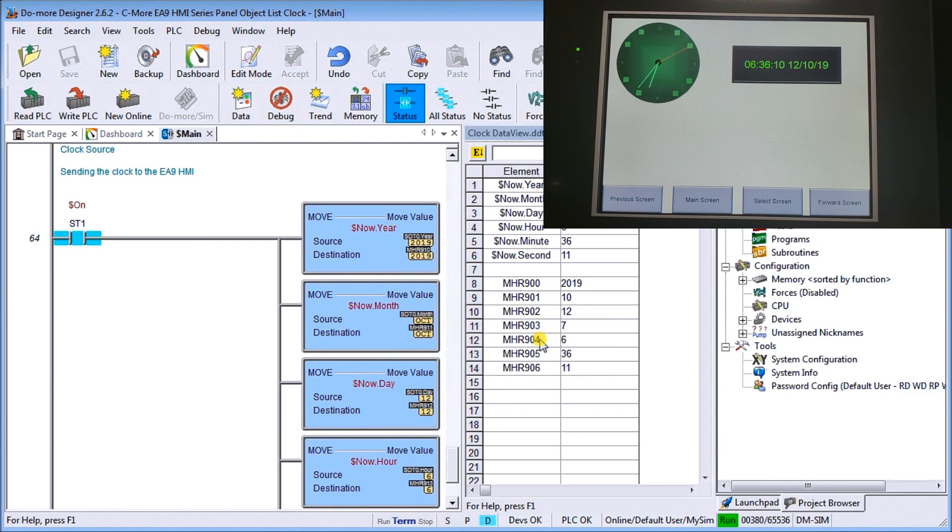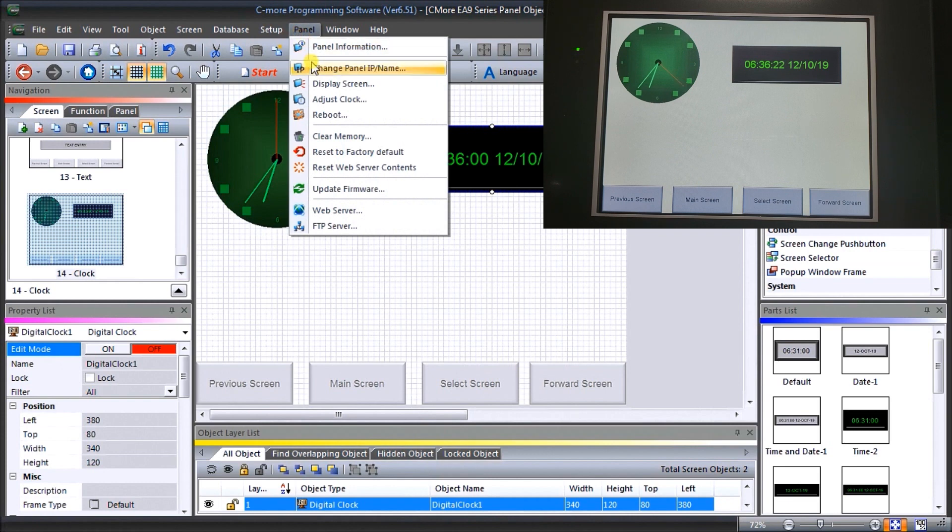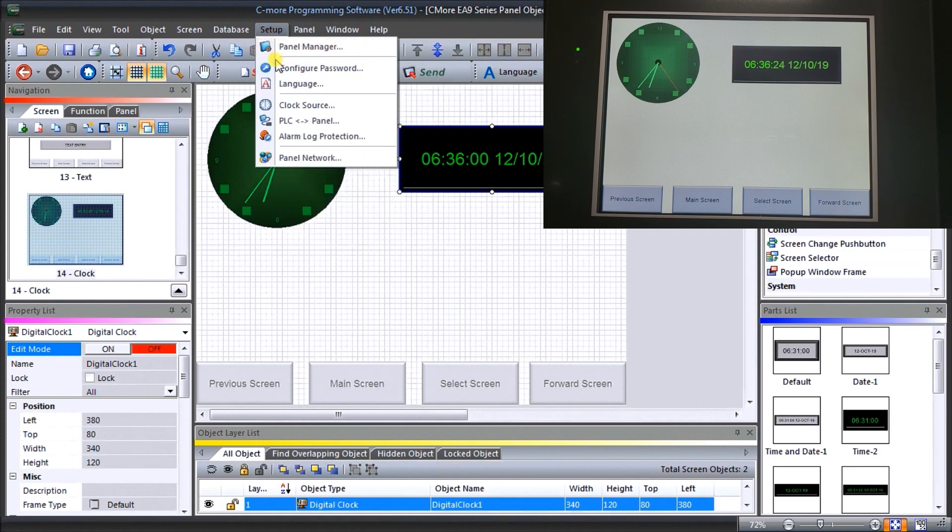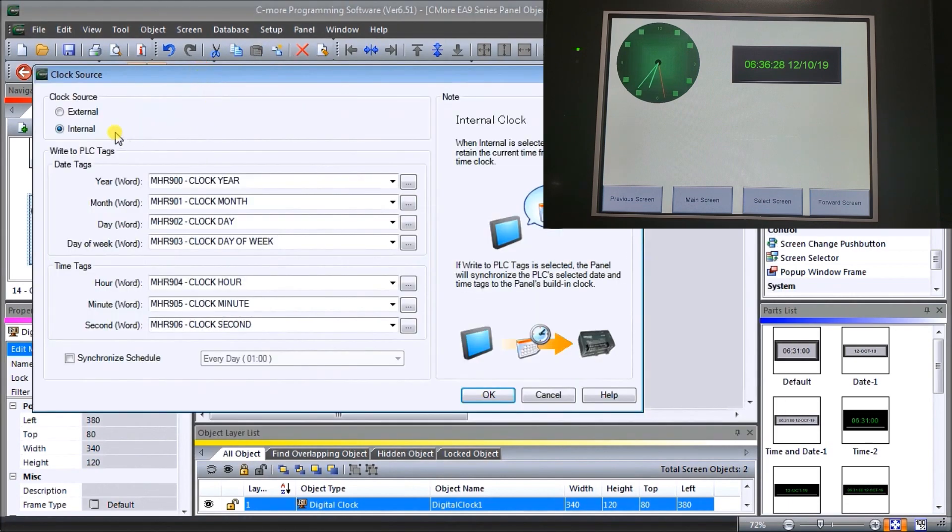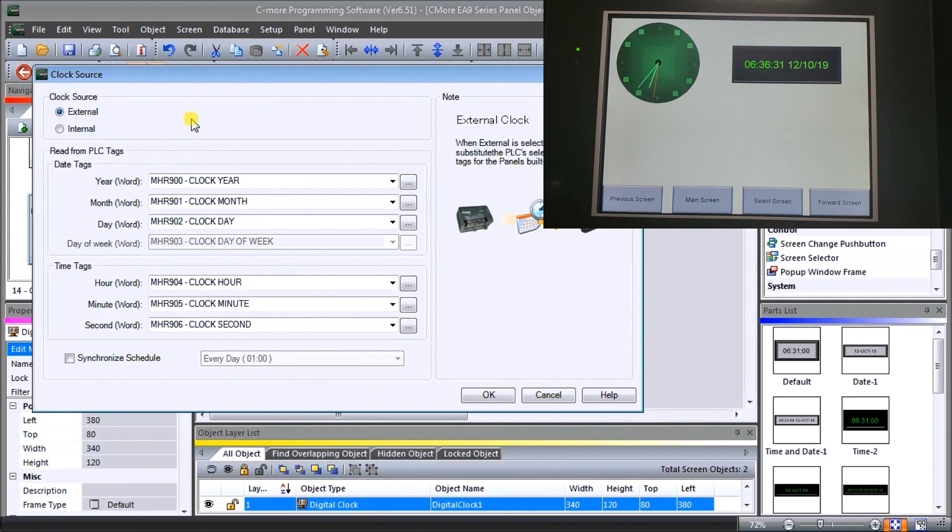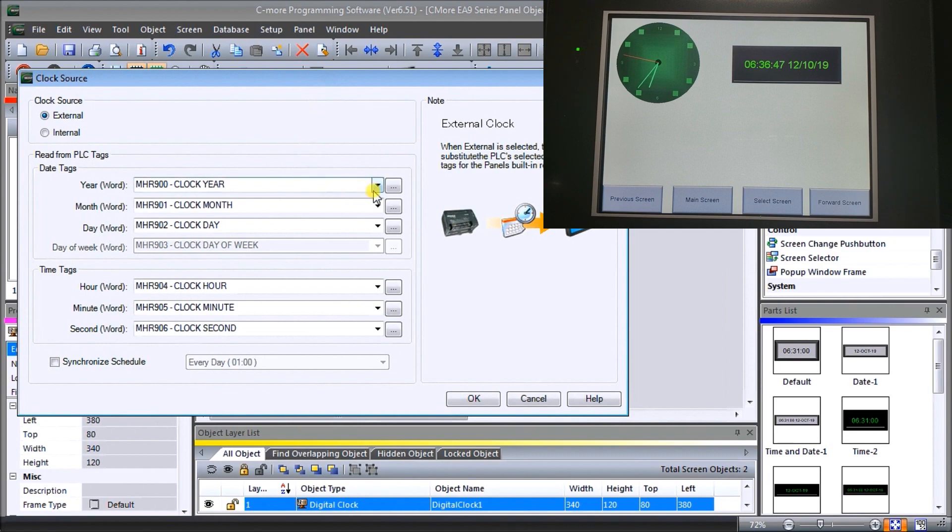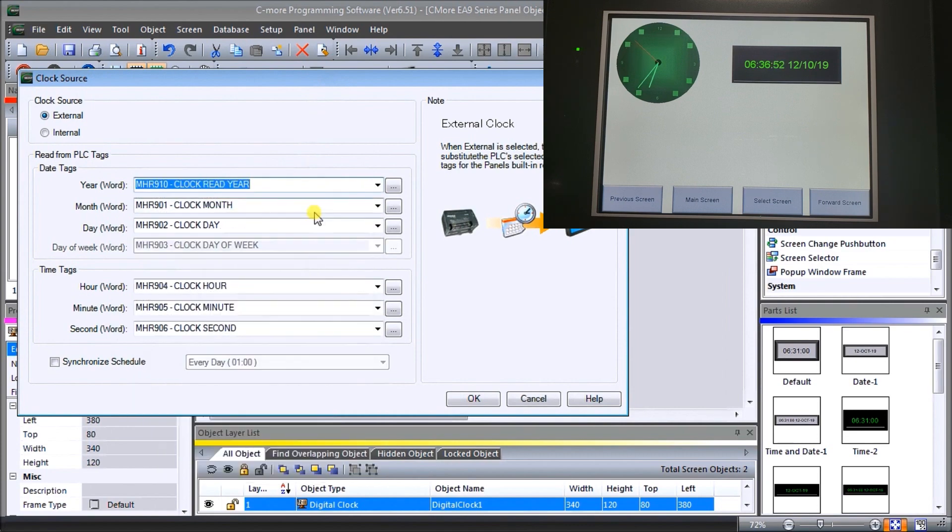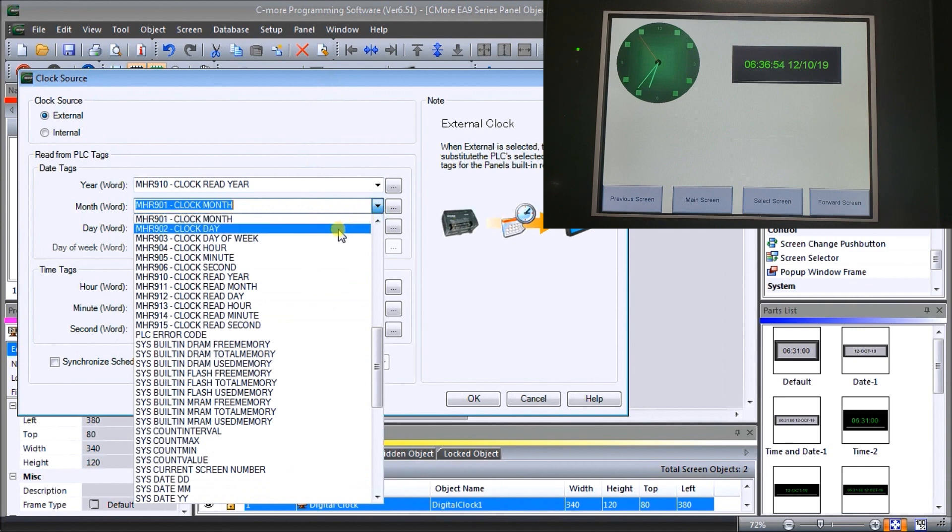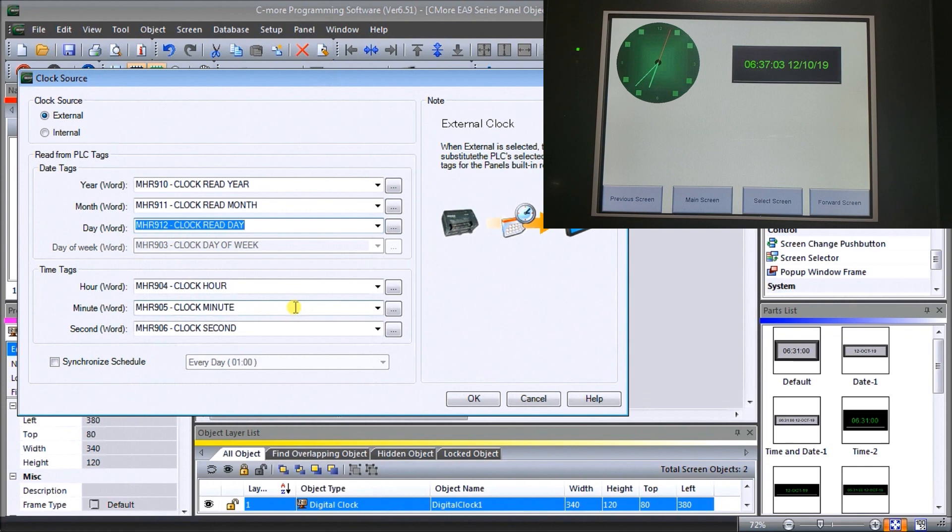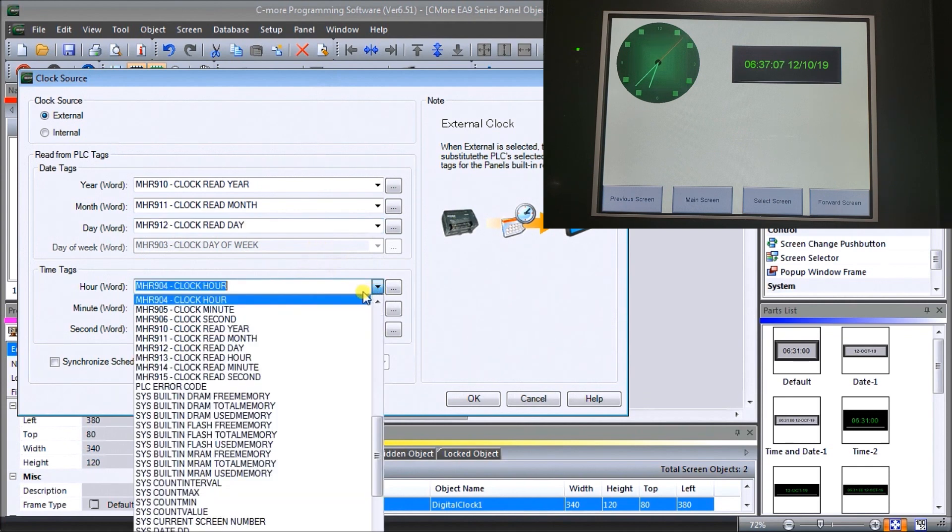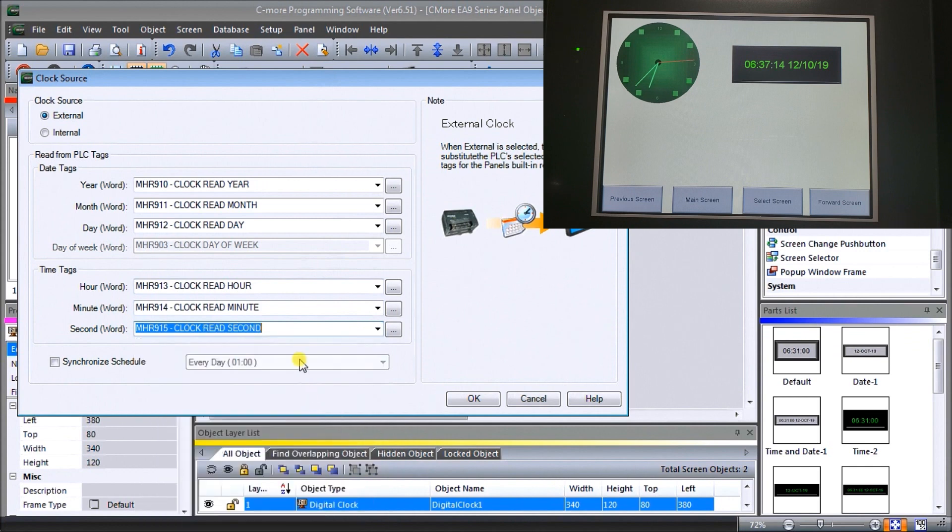Now let's go back to our software and under software let's go to our panel again. We'll look at our setup clock source. Under the clock source we're going to go to external now. So what we're going to do is allow the PLC to write to our internal clock within the HMI, so the PLC will be controlling the time. In this case here, let's change our tags. What we'll do is change our tags to the ones that we have pre-programmed. So we can read the year and read the month and read the day, then what we can do is read our hour, our minute, and second.